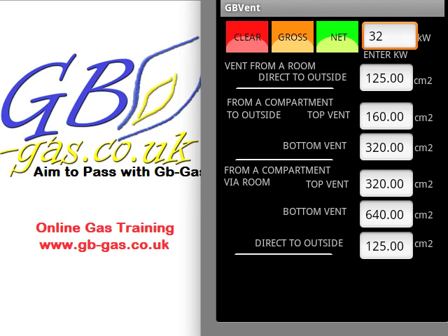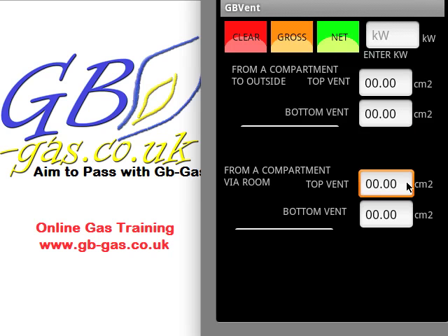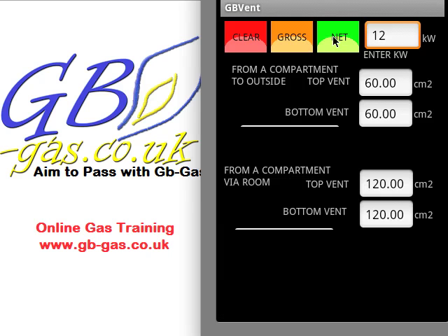If we press the back button on your phone, this will take you back to the main screen where we can have a look at room sealed appliances. When we click on the room sealed appliance button, we have a very similar screen. We input the information at the top right-hand side. Let's make this 12 kilowatts net. So we've got a room sealed 12 kilowatt net appliance in a compartment vented direct to outside — a top vent of 60 cm² and a bottom vent of 60 cm². If it's in a compartment and we're ventilating it into the room, the vents need to be twice the size: a top vent of 120 cm² and a bottom vent of 120 cm².